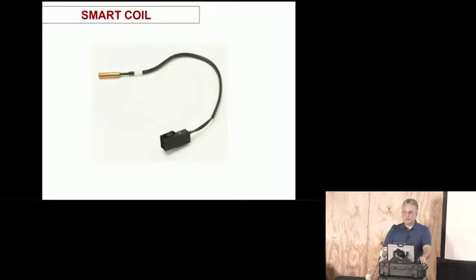yes. So the indoor coil fan stops. Yeah. The system is very intelligent. If you want to turn this conversation into what happens when you first start it, say if you have 20 degrees outside, you don't want to blow cold, right? So the system will increase the compressor speed, which can heat up the refrigerant before it's delivered to the space. And at a certain threshold, then the indoor fan will turn on. So at the get-go, you're blowing warm air.